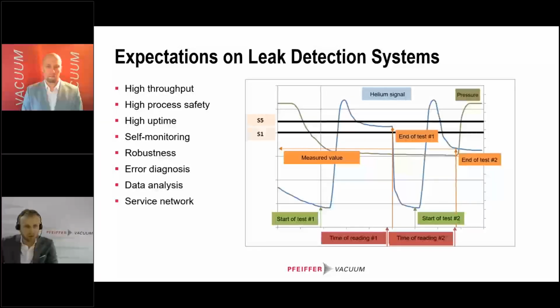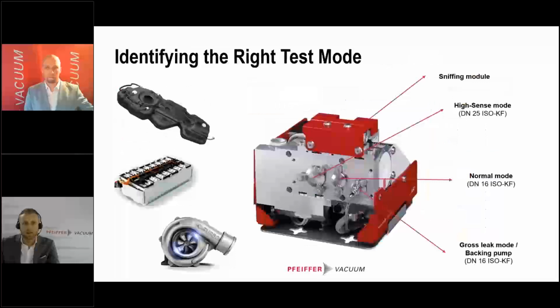You can see here on the right side that this is just an extract of a measured leak rate, and you can already see that you need to consider many things for this. There are different test points, different reading times, different values that you need to consider. In the following slides, we would like to go through each of those with you to explain the individual requirements for the test.